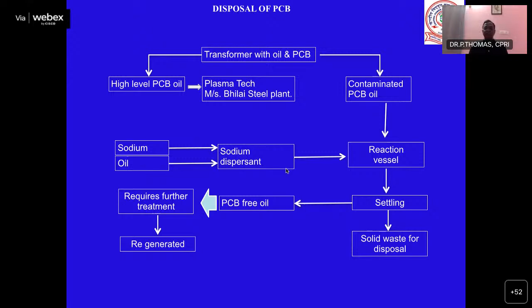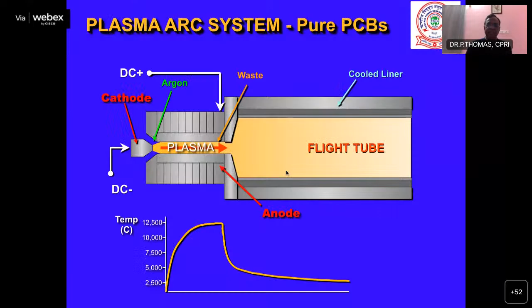The transformers having less than 10,000 ppm will come to CPRI. We call it contaminated oil. This contaminated oil will be taken into a reaction vessel and we add sodium. We call it sodium dispersion. Sodium dispersion means the sodium metal is mixed with oil through some process. I'll show you that. Then you make a dispersion, with sodium and oil at some 40 to 60%. You add that to the PCB oil, so that the sodium in the dispersion reacts with the PCB oil, all PCBs and all chlorine are removed, and the oil is regenerated. For example, if you come to this place, these are the 2 units.